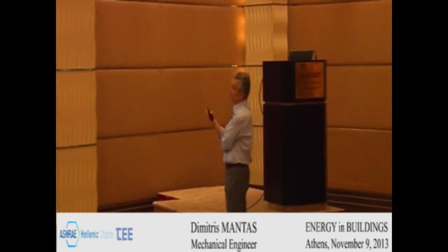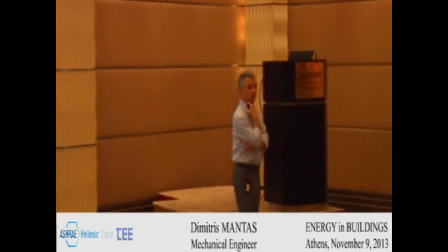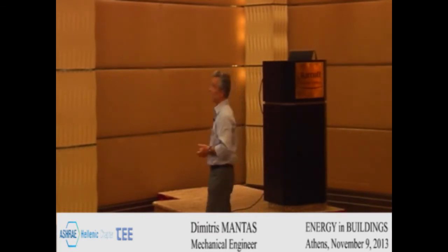Similar comments concern the second building, which is an office building. Again, a very impressive difference between real consumption in heating and in ventilation. Maybe these are correlated. The higher ventilation has required higher heating loads. We are probably losing air quality, and maybe there is a differentiation in the manner that the building is used by its occupants.